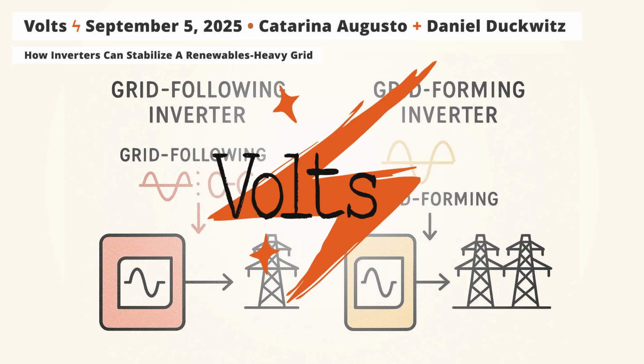So in some ways these inverters do what spinning masses do, but better? Yeah, they can do better. We're working with existing systems, and an existing system will have varying amounts of rotating generators. On a sunny day, there will be almost no rotating machines; on a cloudy day, there will be some; and it depends on wind too. So we're dealing with percentages of rotating machines versus inverters in the range of 10 to 100%, which means you can do better with batteries, but you still need to stay compatible with the old system, which means you shouldn't be too different.